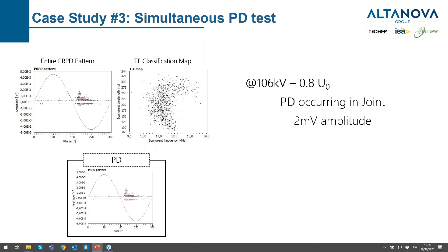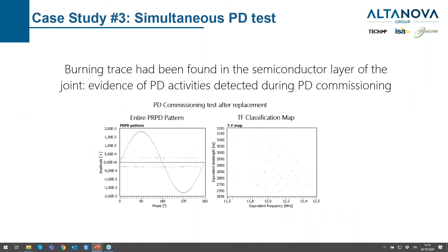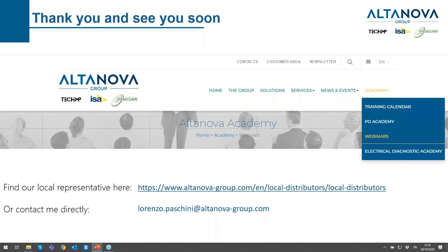At very low amplitude it was possible to see a small PD activity in one joint — 2 millivolts at 106 kV. Following normal procedure, the voltage was increased to 132 kV phase-to-ground to validate the PD without causing joint failure. The full PD pattern became visible and the pulse shape was slightly higher, reaching a peak of 4 millivolts. The test was interrupted and the joint was replaced. After replacement, only noise below 1 millivolt was seen and no PD signal could be detected.